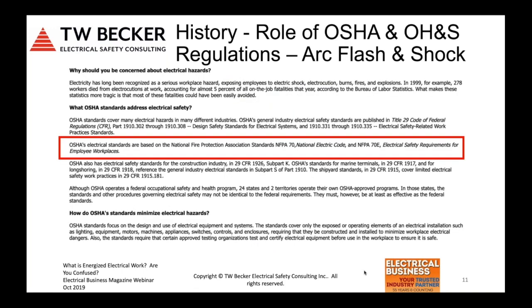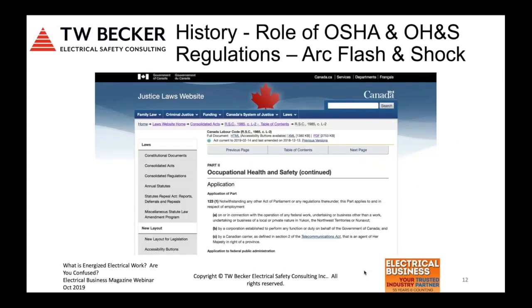Also, you will find that OSHA does specifically say that they reference the National Electrical Code and NFPA 70E in their electrical standards. So it's an informal reference, or they'll utilize content. One point of note is that both NFPA 70 and CSA Z462 are not adopted into OSHA or OH&S law in Canada. So Canada Labour Code Part 2, General Duty Clause, as I mentioned, the electrical safety content is way outdated and focuses on utility workers only.